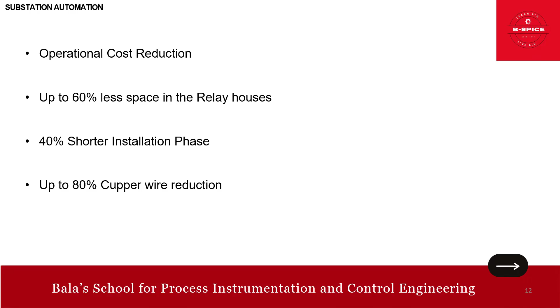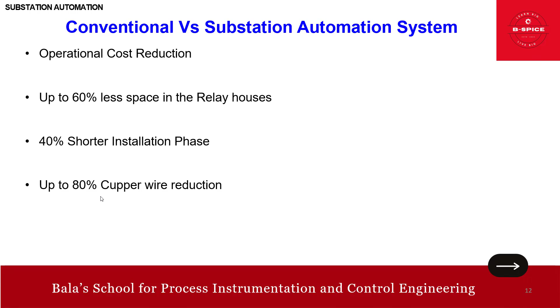Then we'll see the final comparison, friends. When we compare this substation automation system with a conventional system, we can actually get a reduction in operational cost, up to 60% less space in the relay houses - since we're using smart relays, IED devices - and 40% shorter installation phase. Finally, last but not least, up to 80% copper wire reduction because of this IEC 61850 bus.